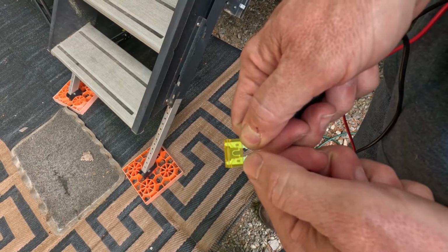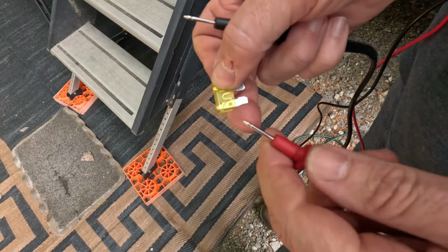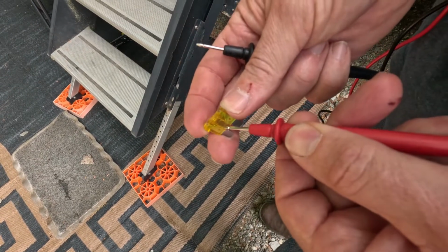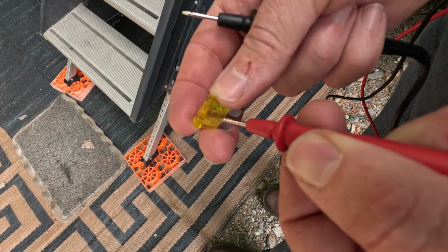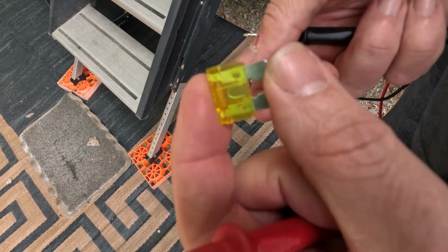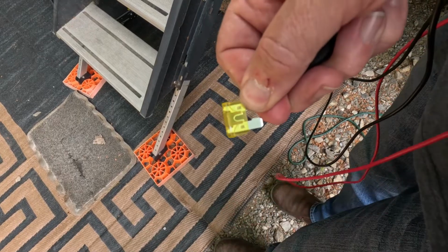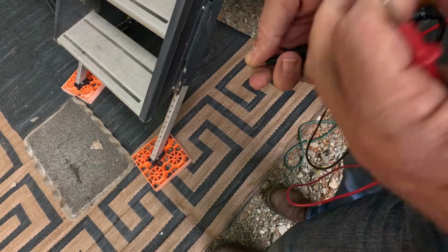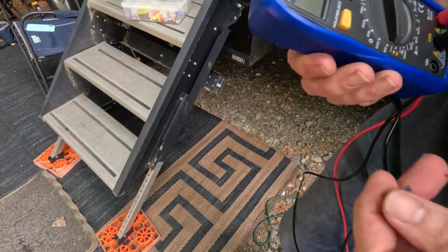If you put it on there and hear that beep, you know that fuse is good. It is very common though for fuses sometimes to just blow or be partially blown, and if it breaks down way down in the corner down here, you may not even see it. So just because a fuse looks good, if you can use the ohm setting on your voltmeter and you get that beep, you can guarantee that that fuse is going to be good.